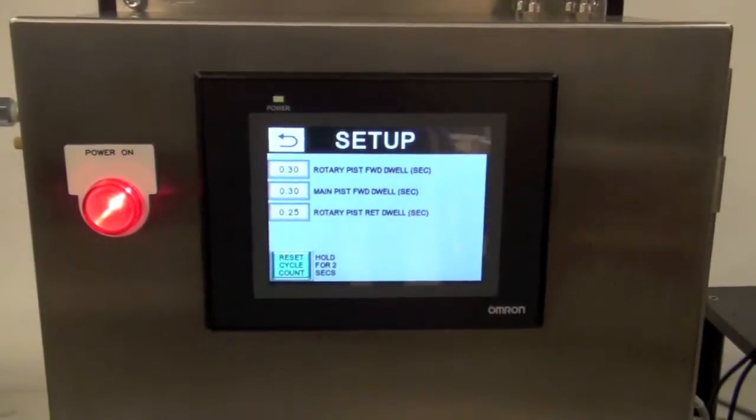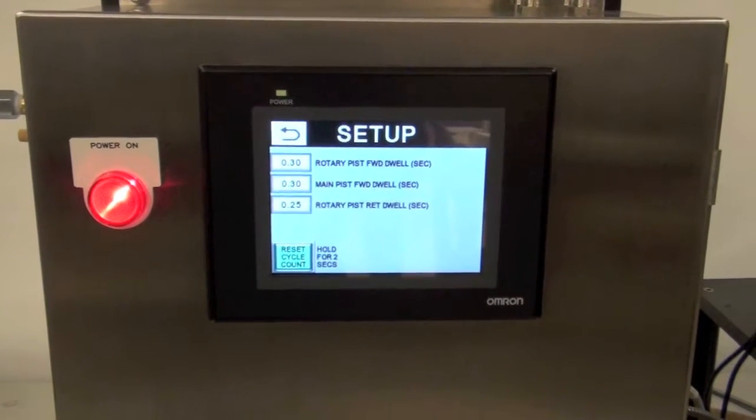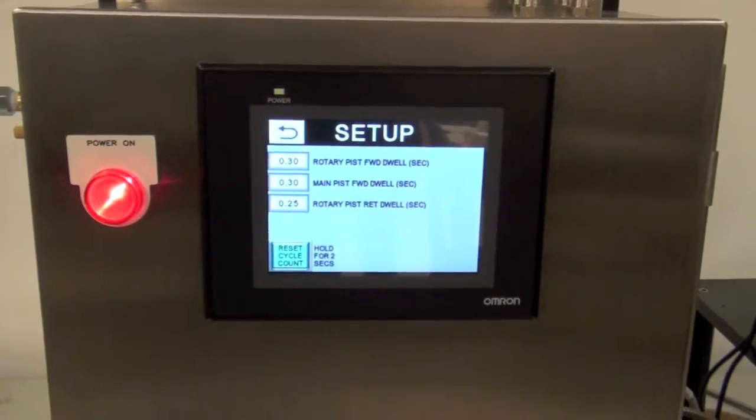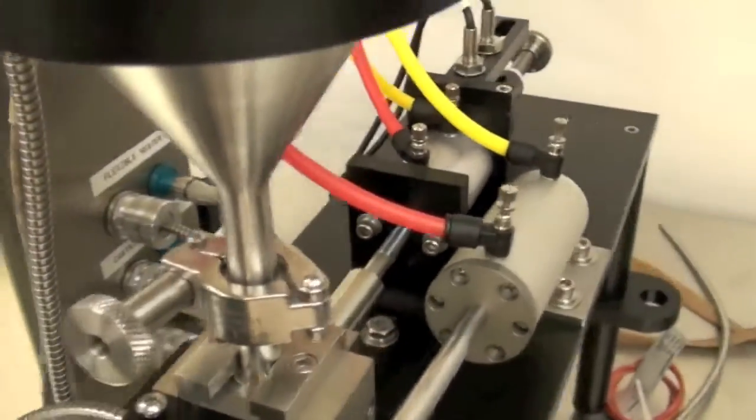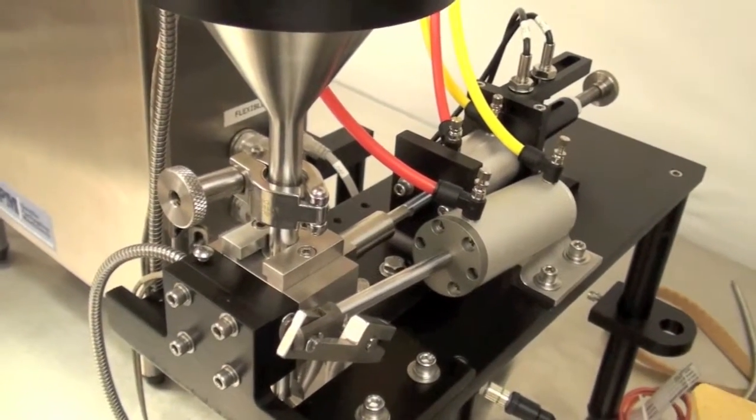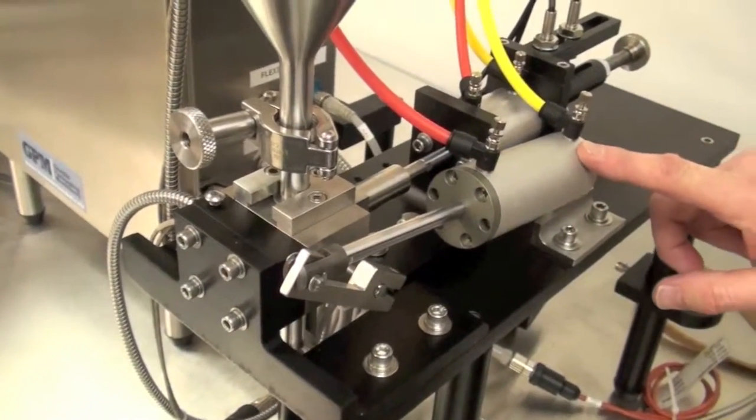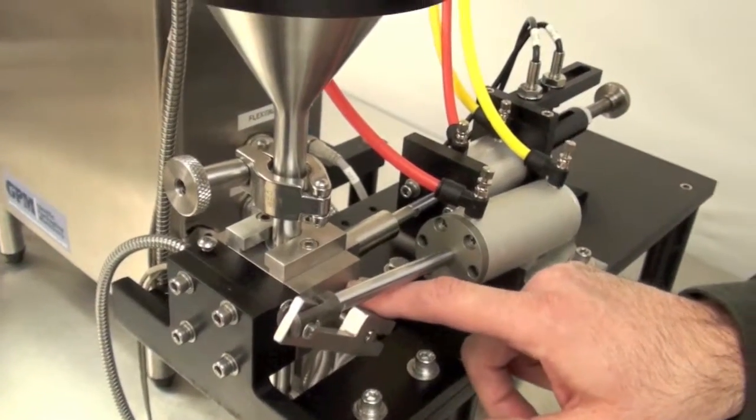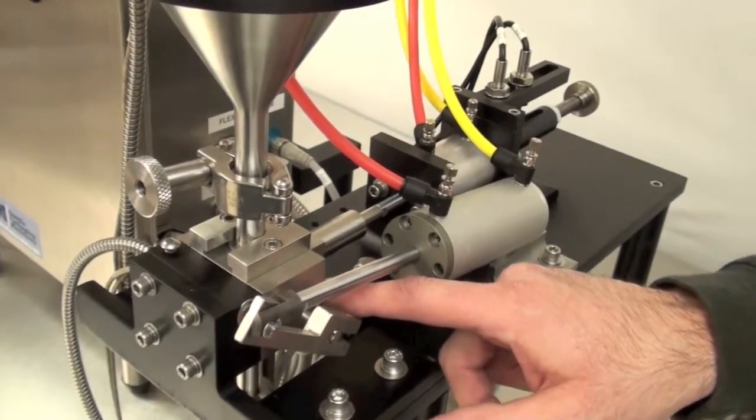This setting indicates how long after the valve opens before the main piston moves forward dosing. So if you look over here, when the product cycle is initiated, the first thing that will happen is that the rotary piston will move back to allow for dispensing.